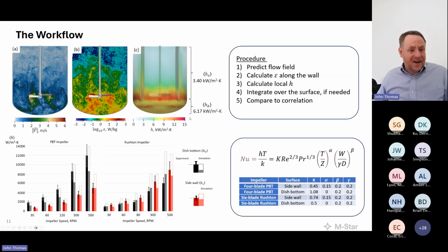And what we can do then is compare. How does this generalized framework do in predicting convective heat transfer against measured data? So there are measured data points for, say, vessels like this. And why I like starting with a vessel like this is because it presents such a heterogeneous flow field. There are regions near the top of the vessel where the convective heat transfer coefficient will be orders of magnitude smaller than what we'll see in the trailing vortex, okay? So if we're going to really test this semi-empirical approach, it better be able to work in a system with large variations in H and EDR.